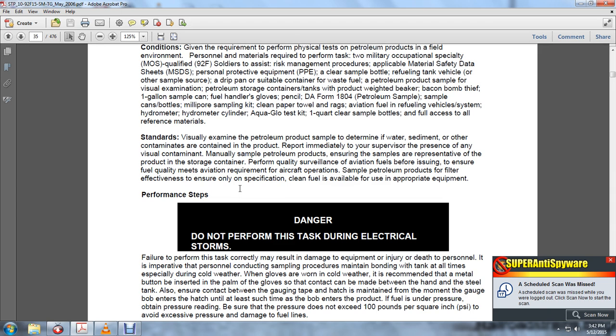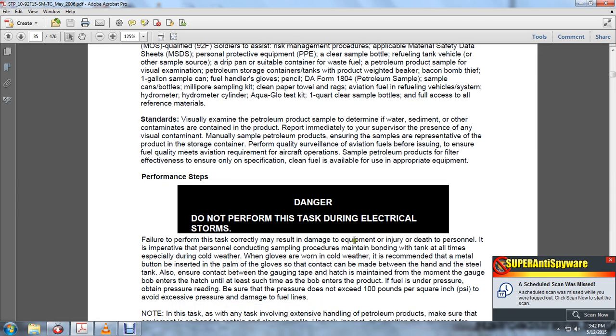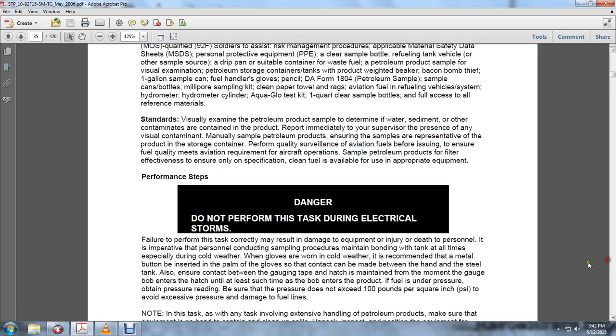Sample petroleum products with filter effectiveness to ensure only specification clean fuel is available for use by the appropriate equipment. Performance steps. Danger: do not perform this task during an electrical storm. Failure to perform the task correctly may result in damage to equipment and injury or death to personnel. It is imperative that personnel sampling maintain the bonding of the tank at all times, especially during cold weather when gloves are worn. In cold weather, the recommended metal button should be inserted with the palm of the gloves so that contact can be made with the hand or steel tank.